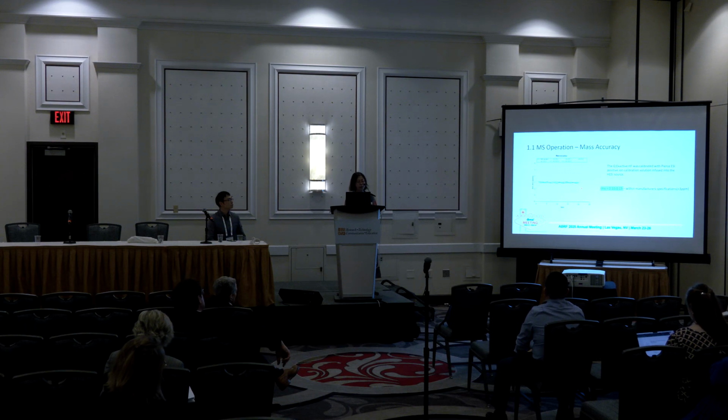And you're looking at the figures, the m/z deviations were estimated by the ppm change. So it is less than 3 ppm. The root mean square is really small, so my instrument mass accuracy is really good.